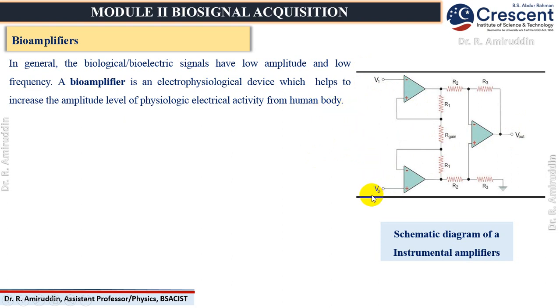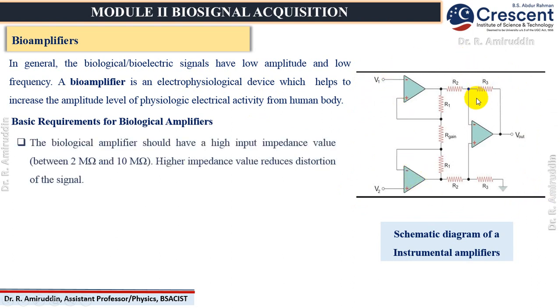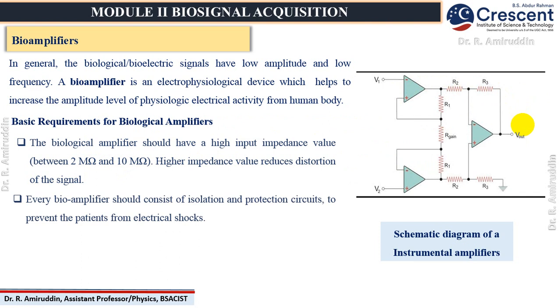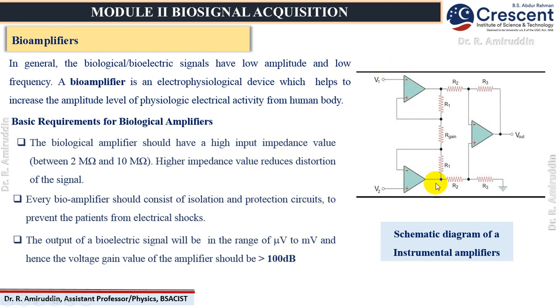This bio-amplifier is an electrophysiological device — in other terms, it is a circuit consisting of op-amps. There are some basic requirements of biological amplifiers. First, the biological amplifier setup should have a high input impedance value ranging from 2 mega-ohms to 10 mega-ohms. Such high input impedance reduces the distortion level of the input signal. Second, there should be a proper isolation circuit and protection circuit so that the patient is restricted from any kind of electrical shock. The output signal will be in the range of micro-volt to millivolt, and hence this bio-amplifier should have a high voltage gain in the order of 100 decibels.